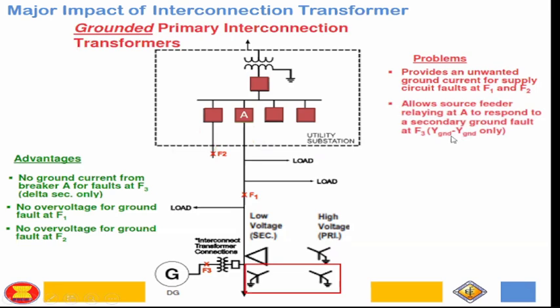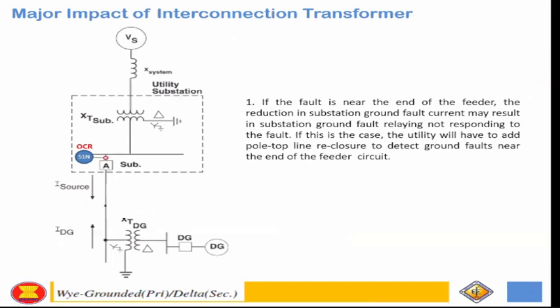Okay? And so, the source feeders allow A to respond to a secondary fault at F3. For the YY, since it is in series, what we saw in the zero sequence connection earlier is that the interconnection transformer impedance is in series with the distribution system. So if there is a fault at the secondary, we need to coordinate the protective devices on the high side, including the feeders, even if there are no reclosers along that line. Okay? So we need to familiarize ourselves with the behavior of our system when we entertain distributed generation.